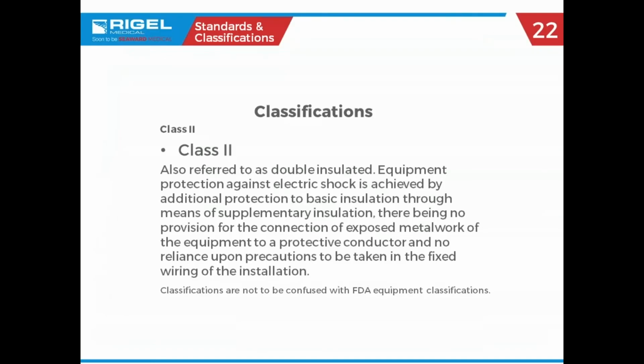Class 2 is double insulated. So it's the plastic box. A lot of your infusion pumps now are plastic box. So the metal chassis is enclosed in this plastic box, and there is no connection going from the plastic, even the screws holding those two pieces of plastic together, to the chassis. So that's double insulated. And here's a surprise.